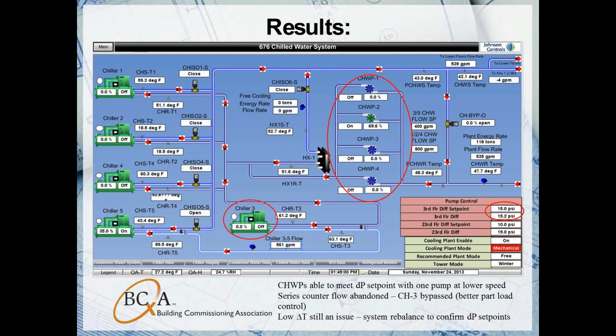And that's exactly right. You can see here, now we are, in fact, meeting our differential pressure set point. It's a fairly cool day. This was a day of testing, so they would typically be in free cooling, but we've got them operating at a very low 118 tons part load with one 400-ton chiller running here. In this situation, we've permanently isolated chiller 3 here.